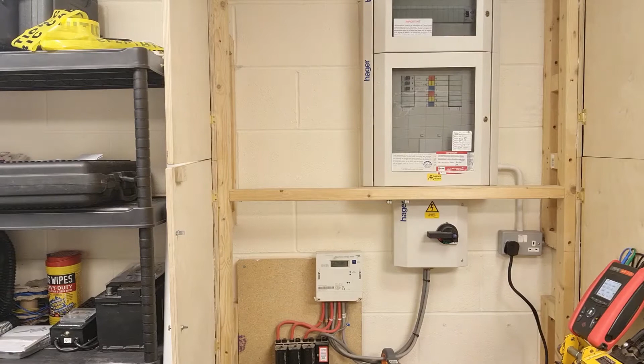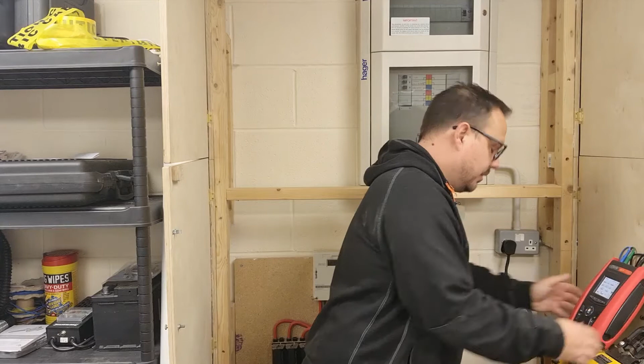It's set to 1200 watts, and I'll just go and turn it up because it will go up to 2 kilowatts, 2 kilowatt heater. So if I pop that up, hopefully the thermostat doesn't kick in like it did just then. And you can see now, if I come a little bit closer, it's measuring 241.5 volts. We've got 8 amps on there, still 50 hertz, and we're showing 1.92 kilowatts. It's jumping between there, and we've got a power factor of 0.99. So I mean, that's what we'd expect to see from that little heater there plugged in the corner. There's no other load on that circuit, and we've got the clamp around the L2 conductor there.